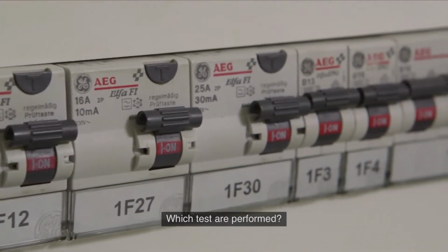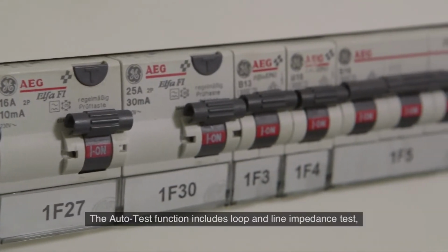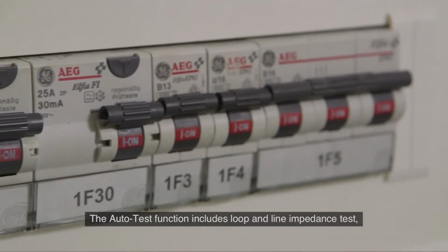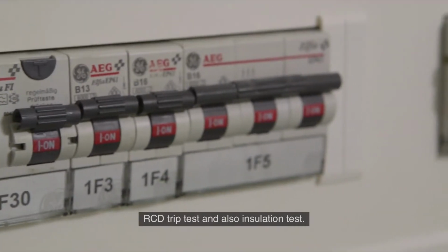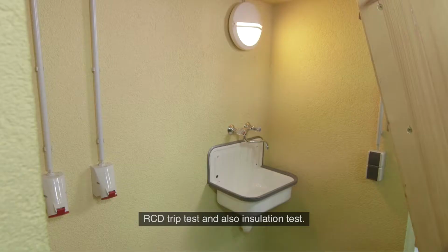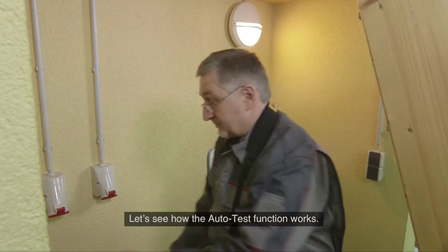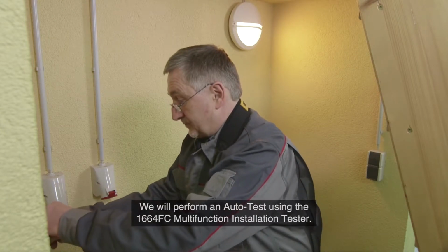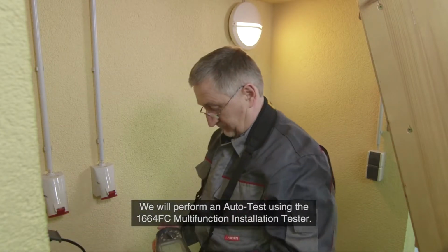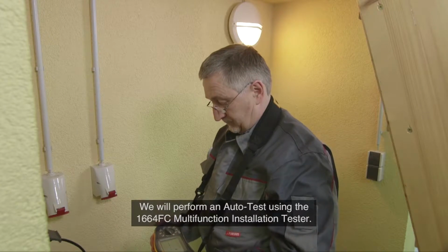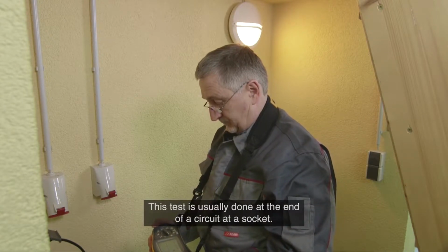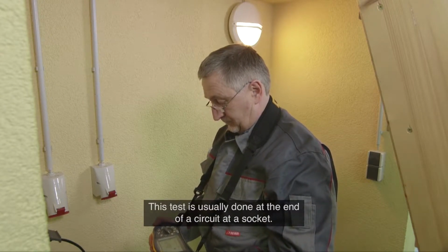Which tests are performed? The AutoTest function includes loop and line impedance test, RCD trip test, and also insulation test. Let's see how the AutoTest function works. We will perform an AutoTest using the 1664 FC Multifunction Installation Tester. This test is usually done at the end of a circuit at a socket.